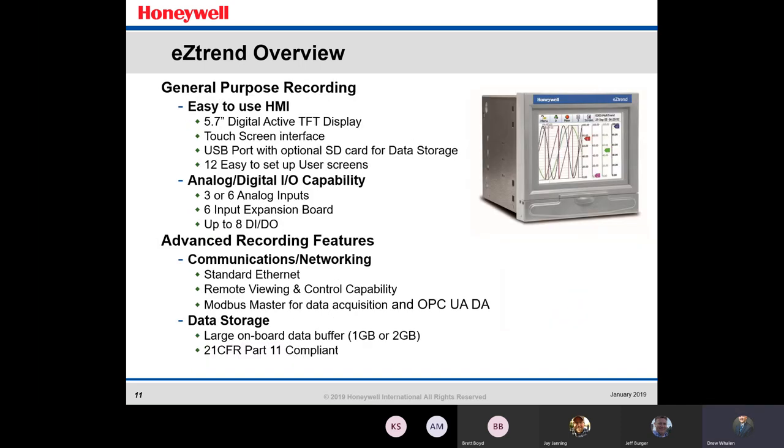The eZtrend is for general purpose recording. You get the 5.7-inch display with 12 easy-to-set-up user screens, a USB port, and an optional SD card for data storage — you can just pop in the USB, grab the data, and transfer it to your computer. Three or six analog inputs with a six-input expansion board if needed. It also has standard Ethernet for communications and remote viewing and control capability, plus Modbus master, with a large onboard data buffer of one or two gigabytes.